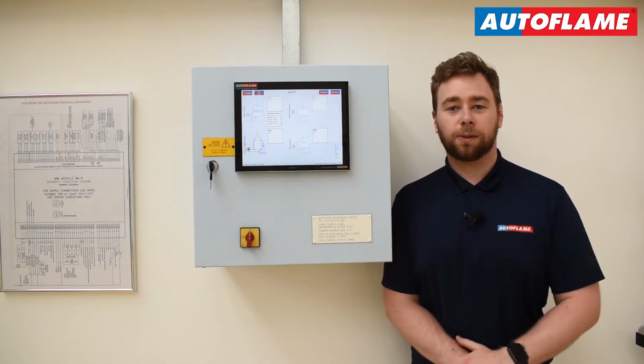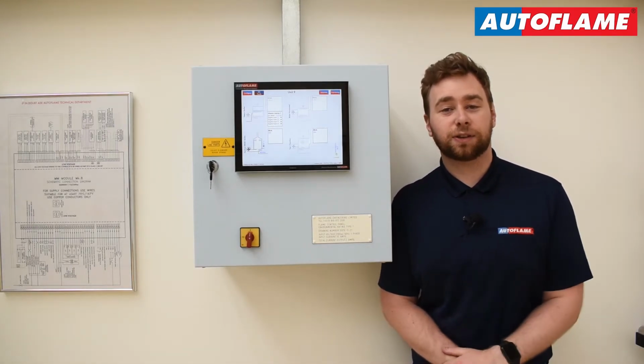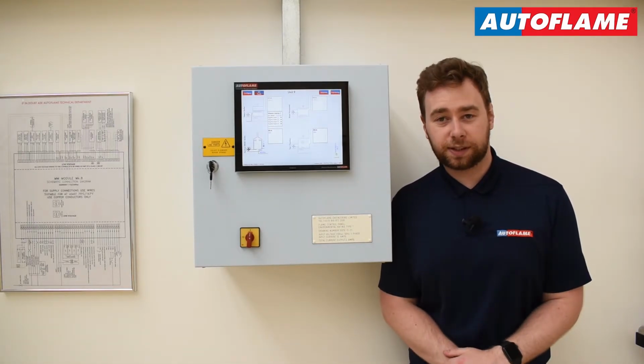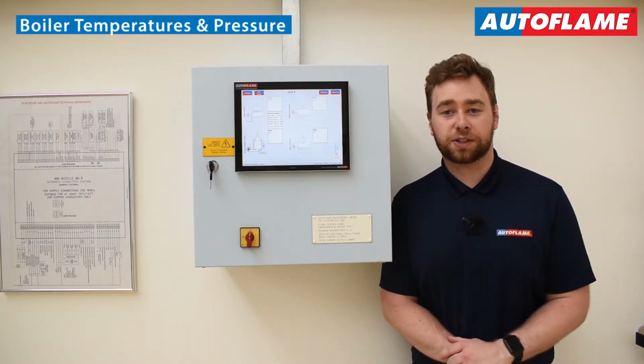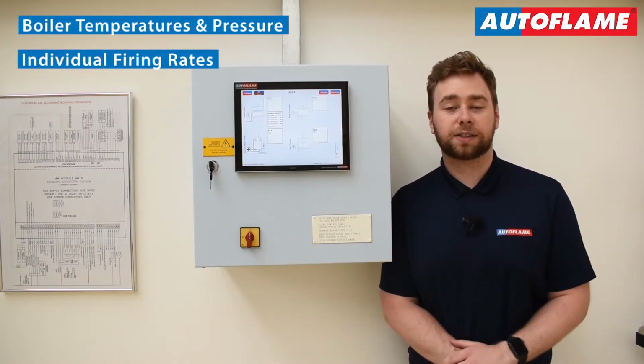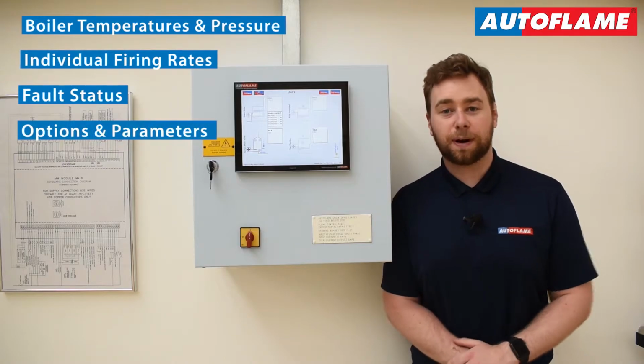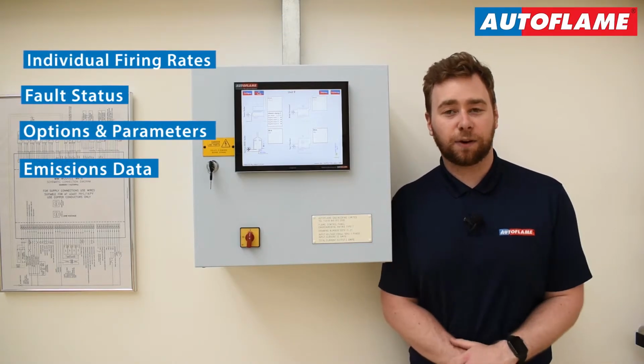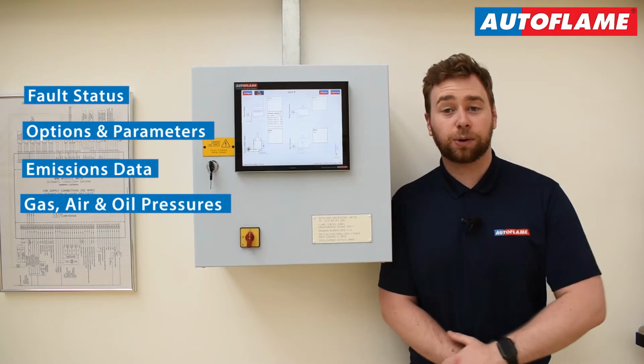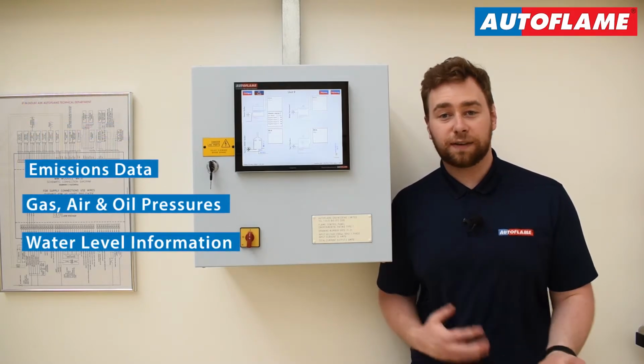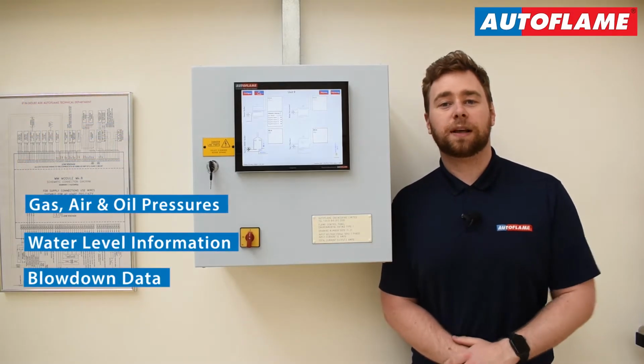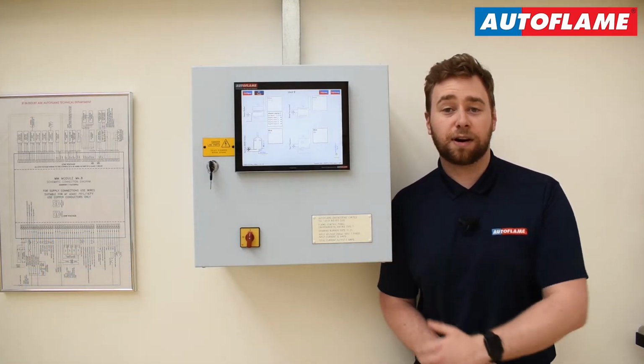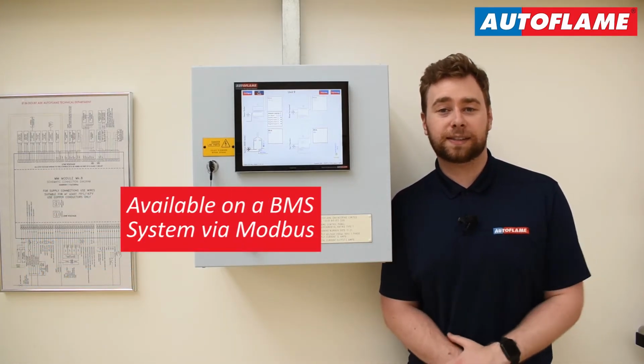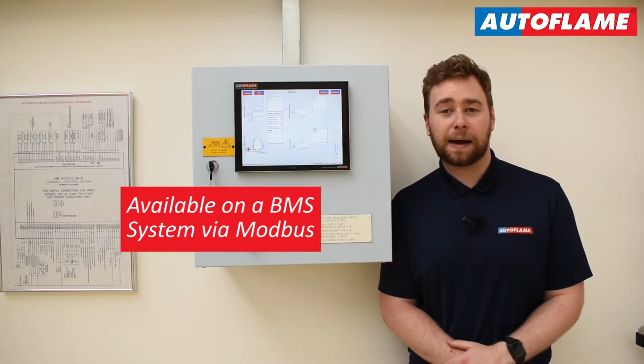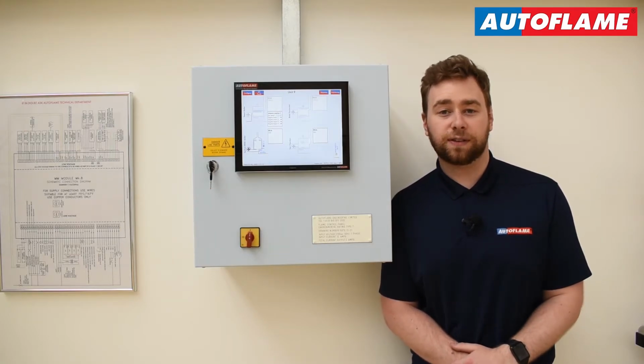Viewable data on the Mk8 DTI and DTI Manager software includes, but is not limited to, boiler temperature or pressure, individual firing rates, fault status, options and parameters, emissions data from the EGA, gas, air and oil pressures, water level information, blowdown data, plus much more. Now, these read and write functions are also available on a BMS system via Modbus. BACnet can be used with the protonode converter.